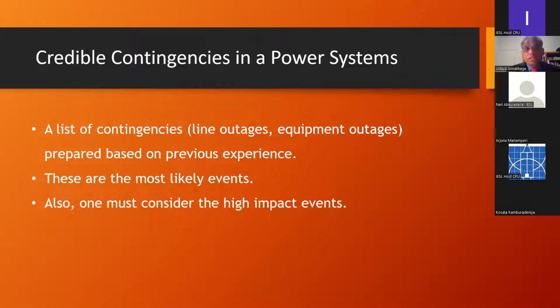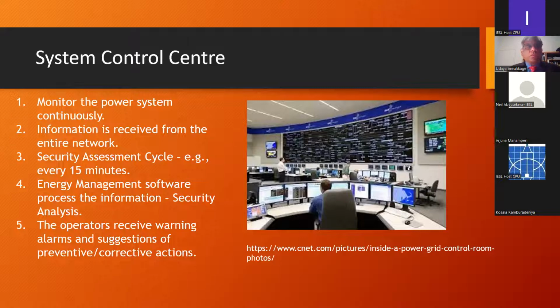And also one must consider the high impact events. Those are the events that are less likely to happen, but if they happen, the impact is going to be high. So with some engineering experience, operating experience, one has to come up with this list. It's called credible contingency, or list of credible contingencies. And that list is very specific to a given power system network. Now, the System Control Center has the task of maintaining the security of the power system, continuity of supply to the consumers.